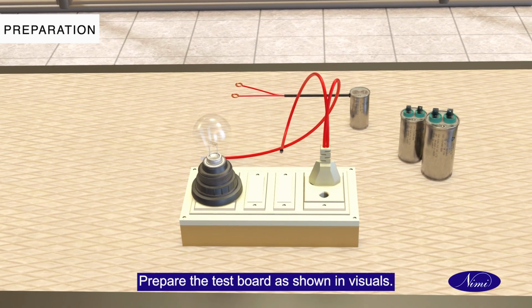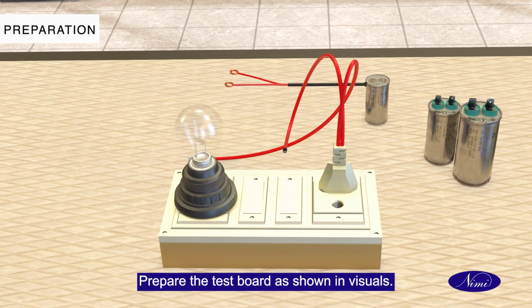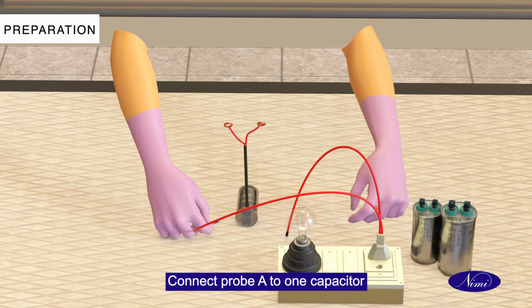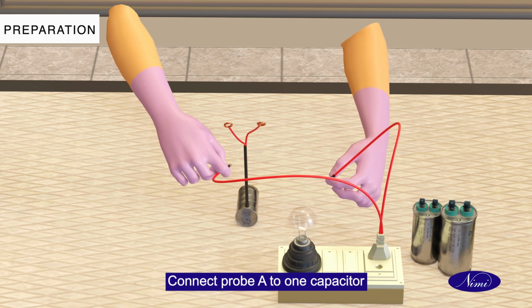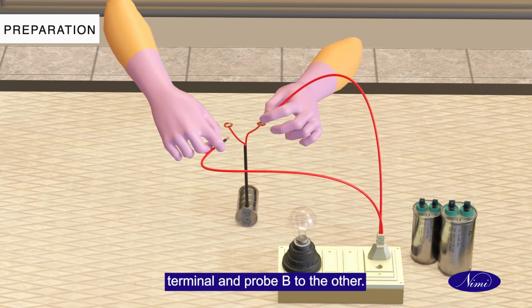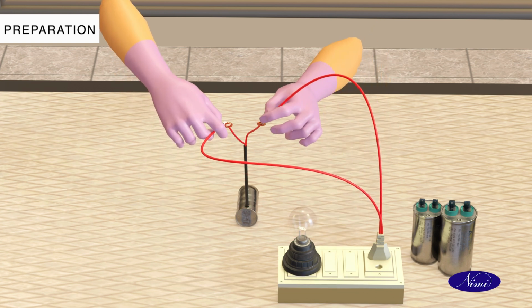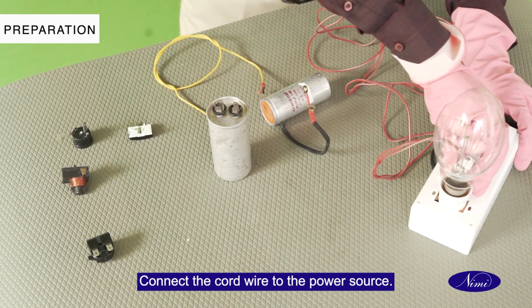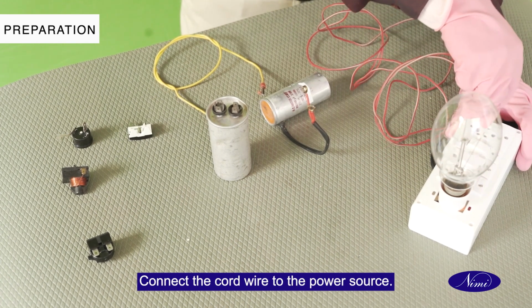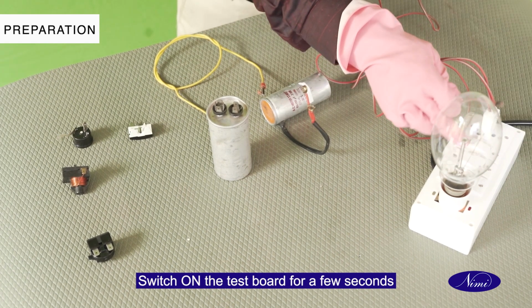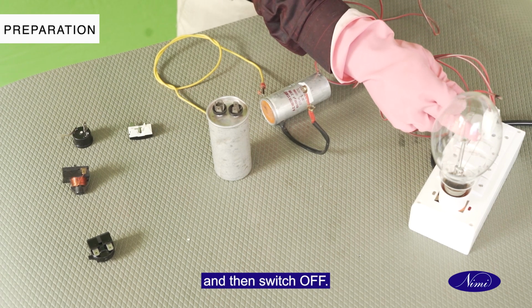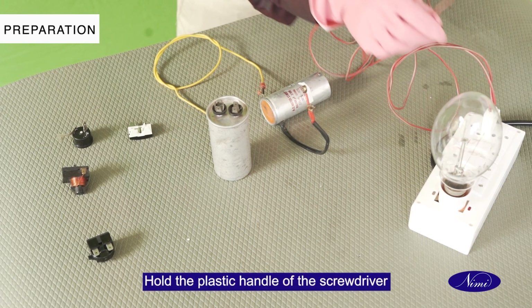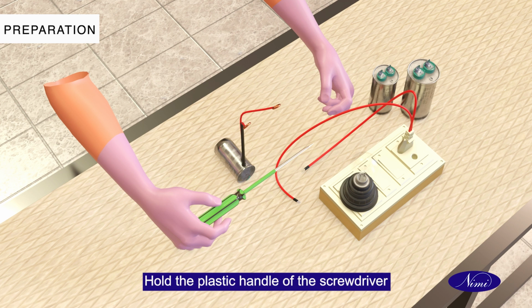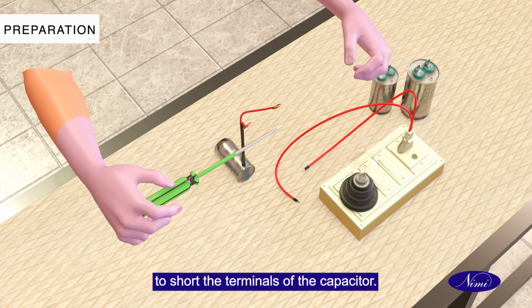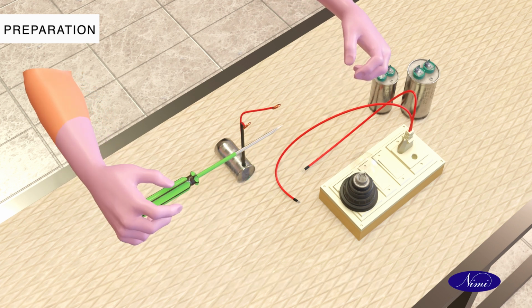Prepare the test board as shown in visuals. Connect probe A to one capacitor terminal and probe B to the other. Connect the cord wire to the power source. Switch on the test board for a few seconds and then switch off. Hold the plastic handle of the screwdriver to short the terminals of the capacitor.